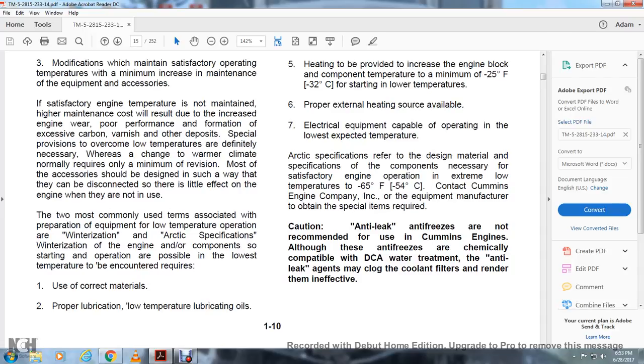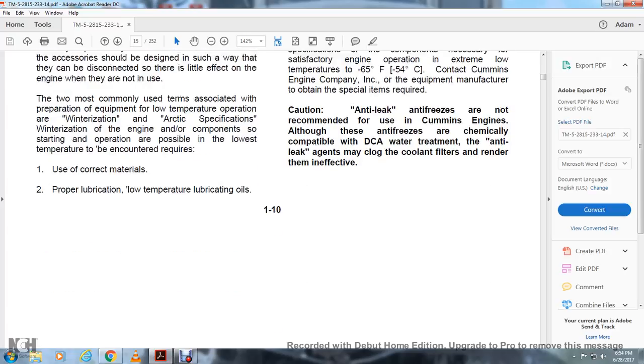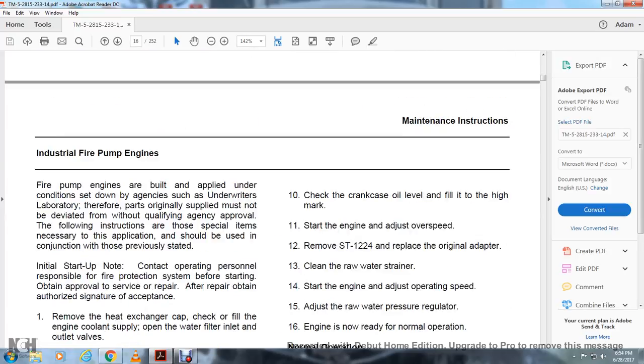Caution: anti-leak antifreezes are not recommended for use in engines, although the antifreeze is chemically compatible with DCA water treatment. The anti-leak agents may clog the coolant filters and render them ineffective. Fire pump engines are built and applied under the conditions set down by the agency under the laboratory listing. They are not to be deviated from the originally supplied configuration without the qualifying agency's approval.